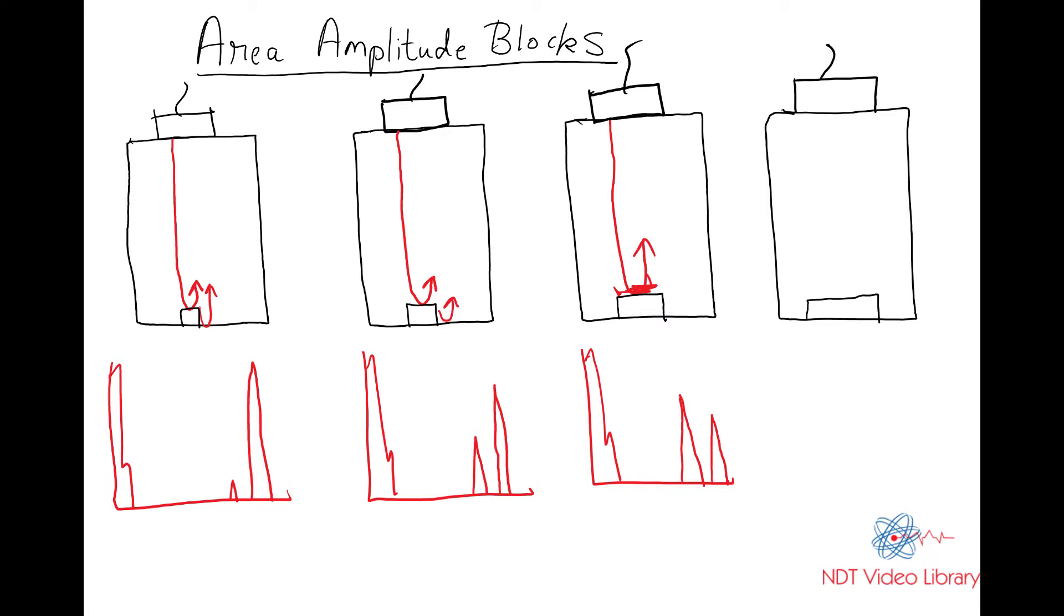Same thing for the fourth one. Maximum sound will be reflected from the flat bottom hole, so it would be the tallest peak. And then the back wall would be the shortest. Does that make sense?